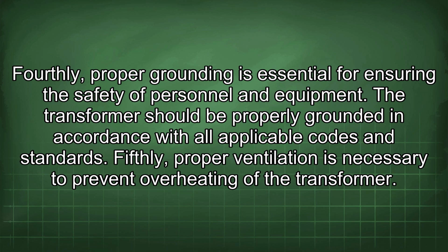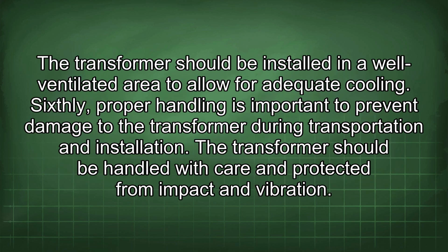Fifthly, proper ventilation is necessary to prevent overheating of the transformer. The transformer should be installed in a well-ventilated area to allow for adequate cooling. Sixthly, proper handling is important to prevent damage to the transformer during transportation and installation. The transformer should be handled with care and protected from impact and vibration.